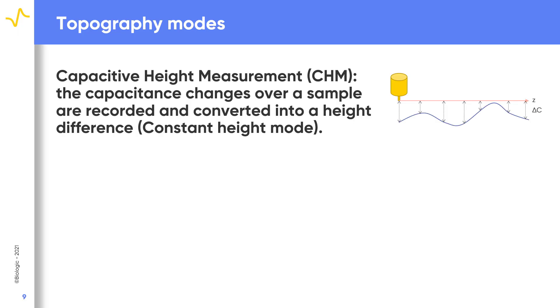On the Biologic SKP 470, there are two experiment types which can be used to measure sample topography. The first is the capacitive height measurement, or CHM, which is a constant height method of measuring the sample topography. In this mode, the probe Z position is maintained throughout the measurement. As the probe-to-sample distance changes, the measured capacitance changes, and it is this change in probe-to-sample distance, determined from the change in capacitance, which is plotted. Because CHM measurements are constant height, they are most useful for flat samples, and can also be performed in sweep scan mode for fast topography measurements.